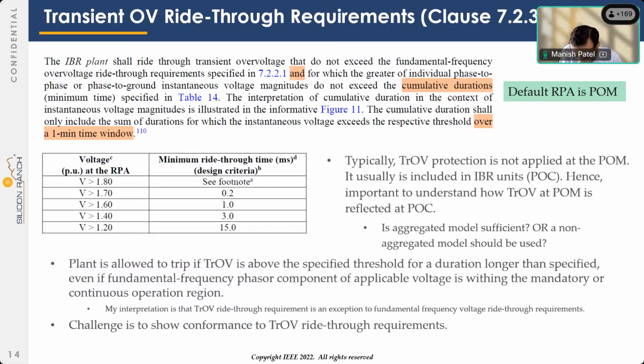Transient overvoltage ride-through requirements. You all might have heard this. This is clause 7.2.3. This has been the nightmare of my life, I guess. I was in charge when we were trying to come up with these requirements when 2800 was written. Again, the default applicability is POM. The standard says that the IBR plant shall ride through transient overvoltage that does not exceed the fundamental frequency overvoltage ride-through requirements in 7.2.2.1 and the rest of the things.